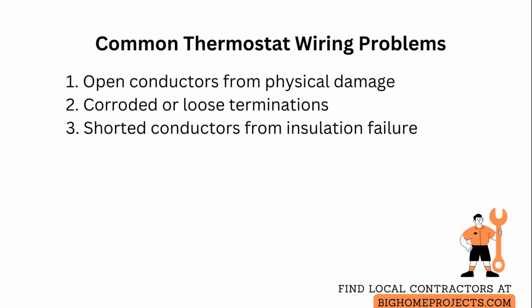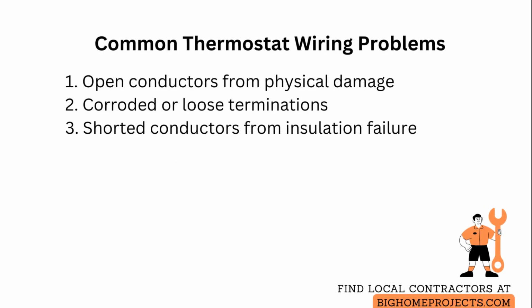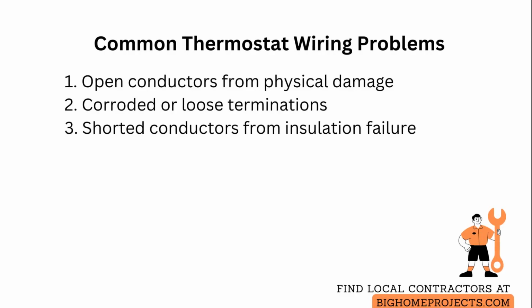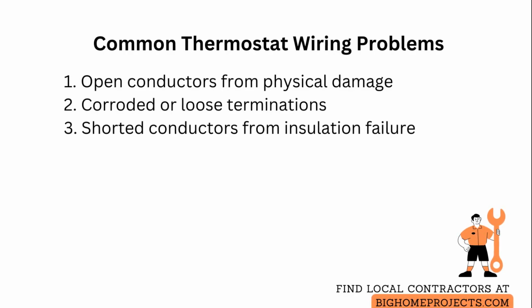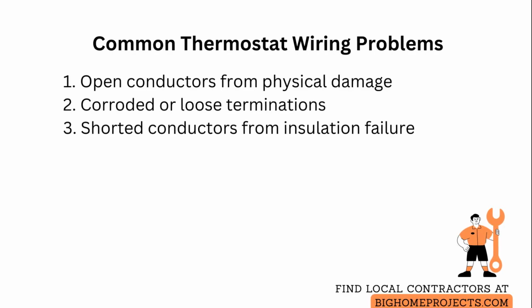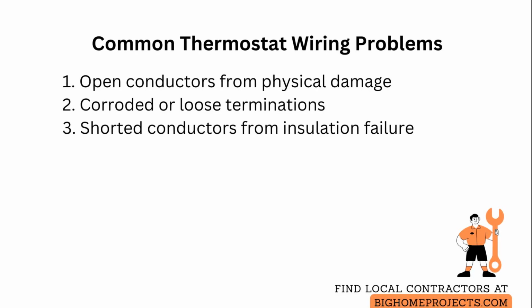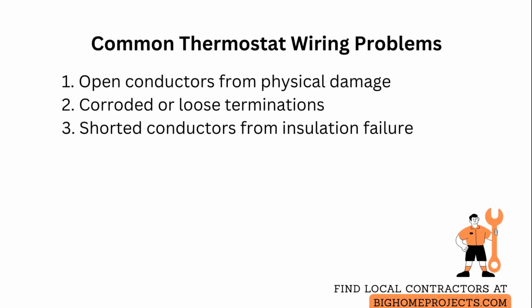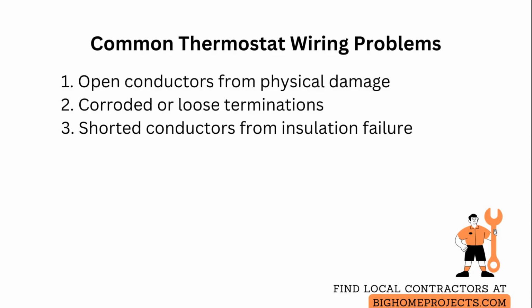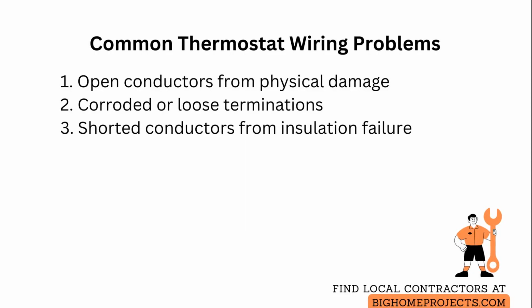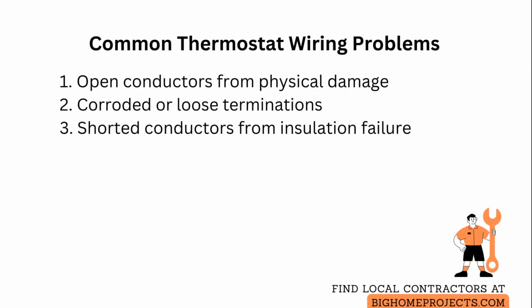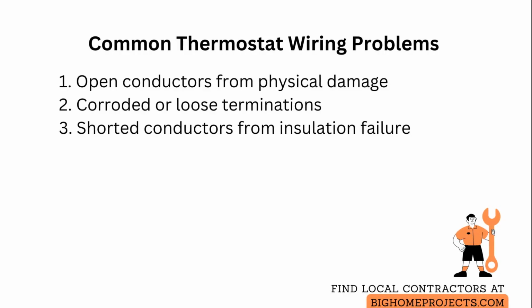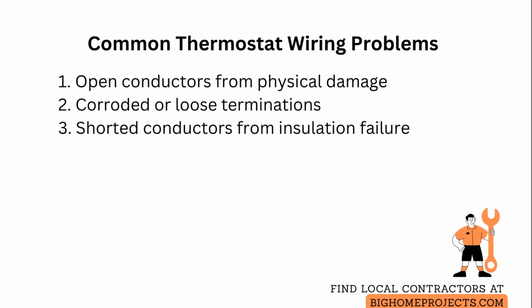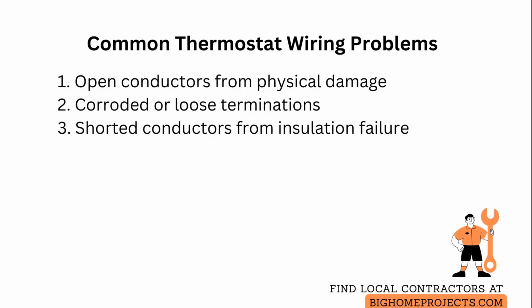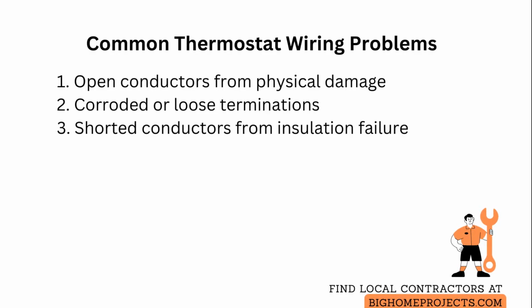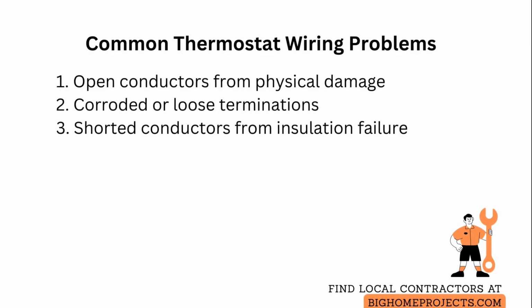Common problems are open conductors from physical damage, which will show infinite resistance on a meter and require replacement of the run or splice. Corroded or loose terminations, which you fix by cleaning, reterminating, and securing connections, and shorted conductors caused by insulation failure, which will show low resistance between conductors and must be isolated, repaired, or replaced to prevent control circuit faults and potential transformer overload.